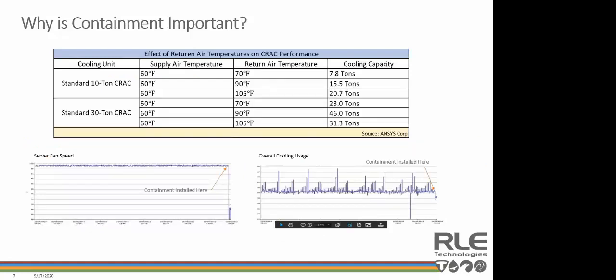When containment is applied to a data center, the return air tends to be warmer due to reduced mixing of air. If the return air temperature can be increased, cooling units become much more efficient. The chart at the top of the screen is a good example of how much more or less a CRAC unit can actually provide based on return air temperature.